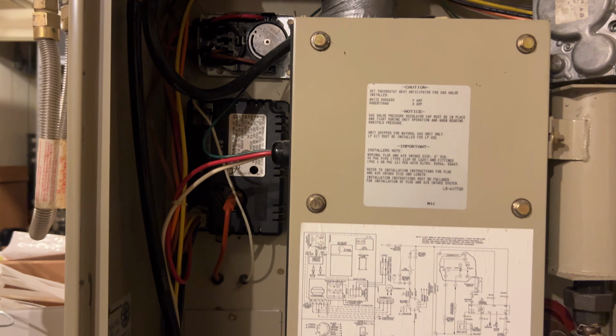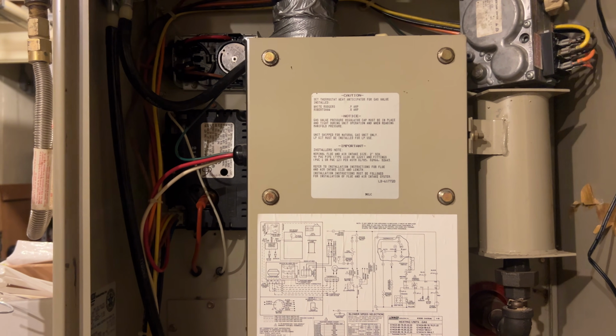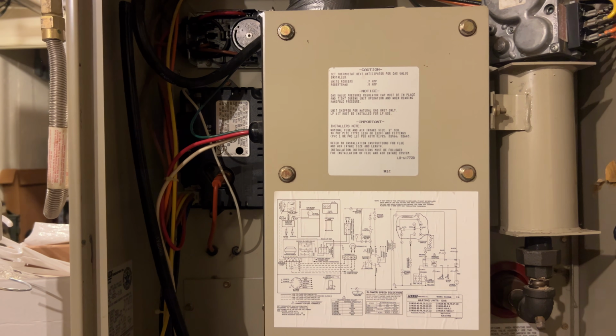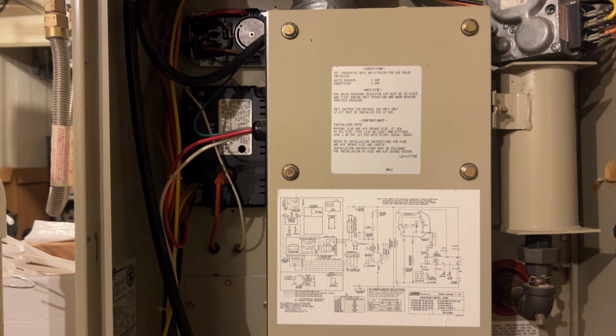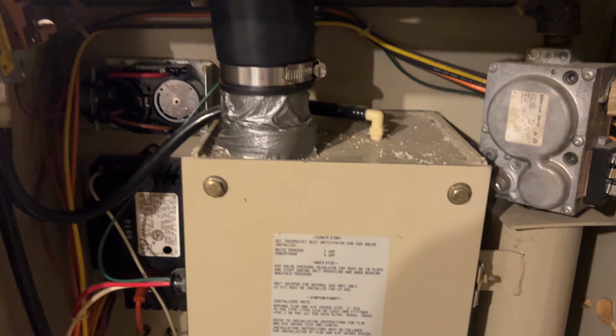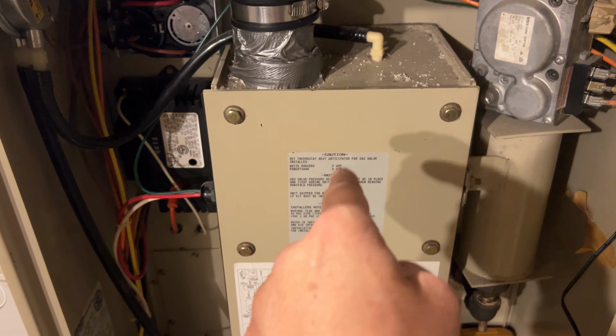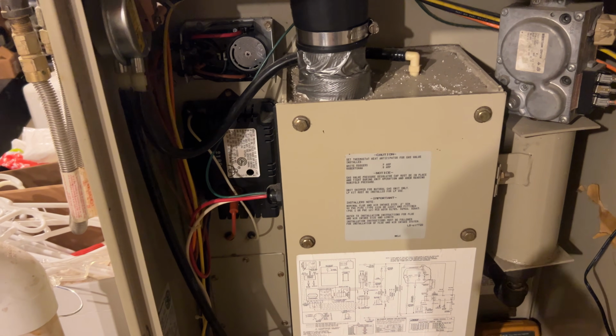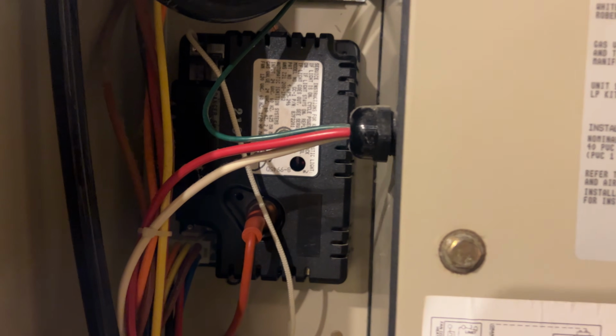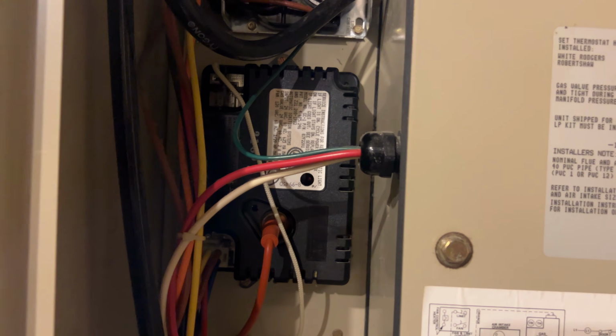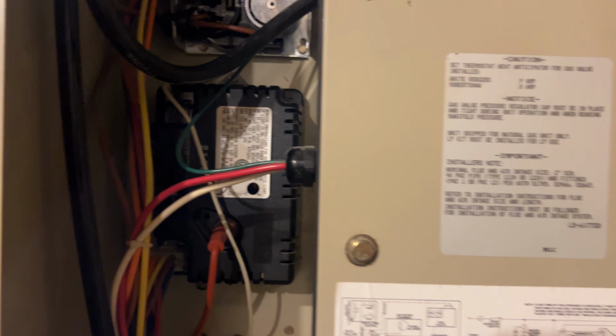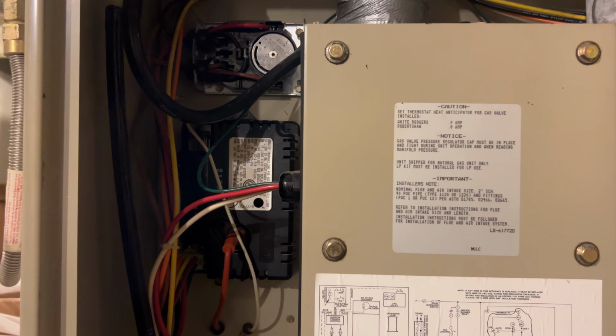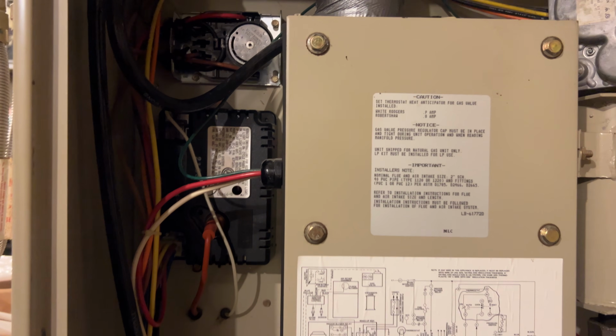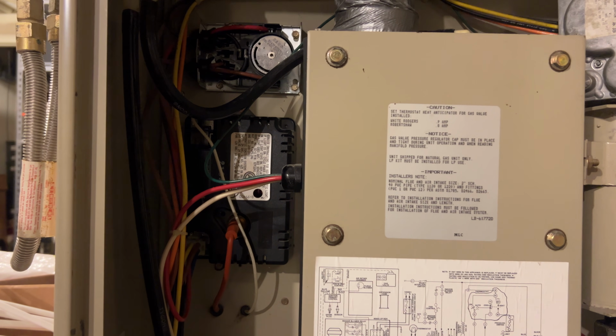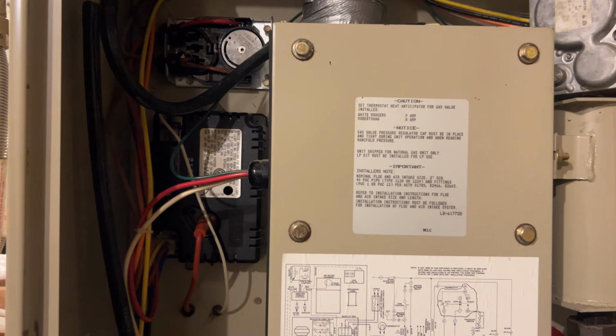See if it tries again, because that did not sound healthy at all. It's trying again, you hear that? There's a purge fan inside here, and I think the bearing is going out on it, because that doesn't sound good. Sounds terrible, but I wonder if it'll go ahead and start regardless.